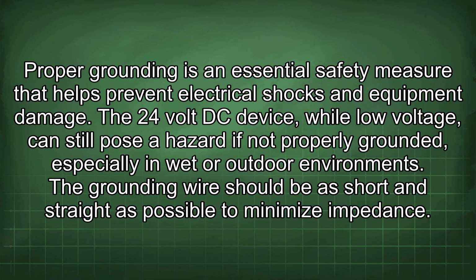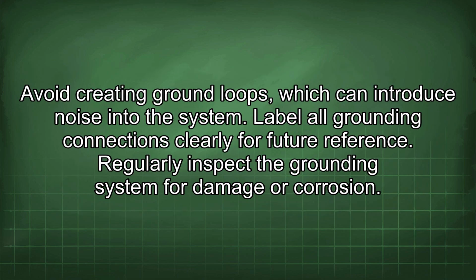The 24-volt DC device, while low voltage, can still pose a hazard if not properly grounded, especially in wet or outdoor environments. The grounding wire should be as short and straight as possible to minimize impedance. Avoid creating ground loops, which can introduce noise into the system. Label all grounding connections clearly for future reference. Regularly inspect the grounding system for damage or corrosion.